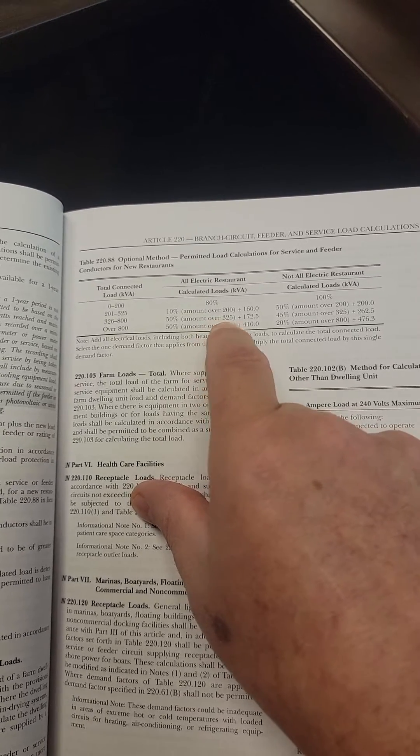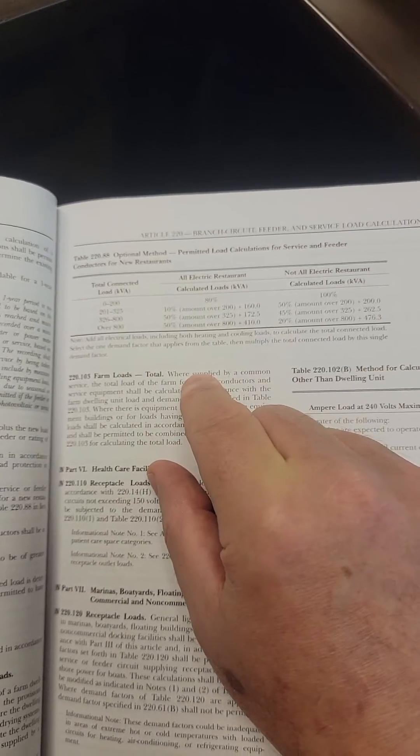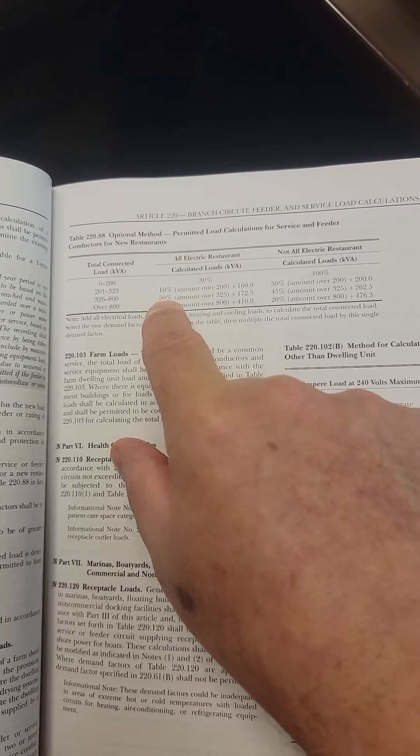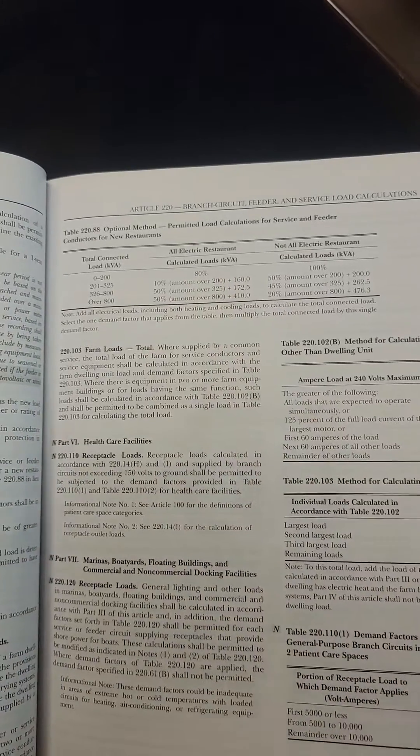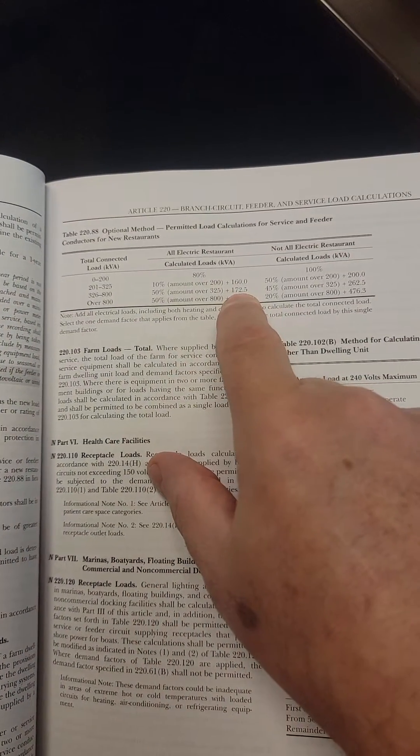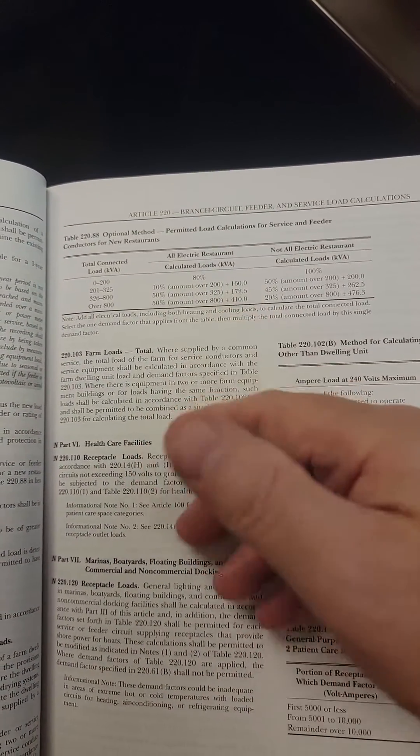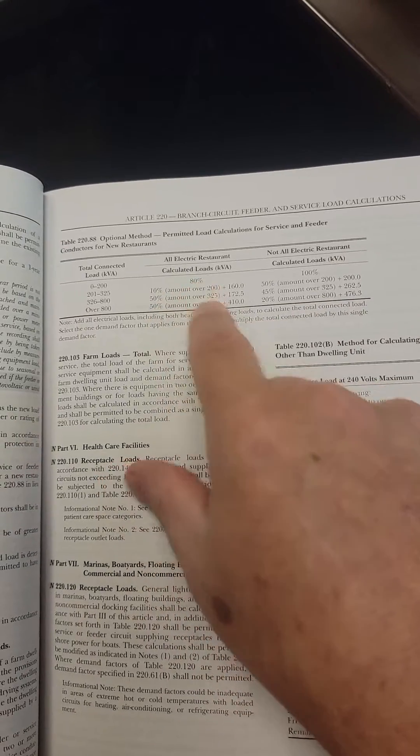You take away 325 from it. The amount that you have, the remainder, you multiply that by 50%. And whatever that value is, you add 172.5 to that. And that is your calculated load.